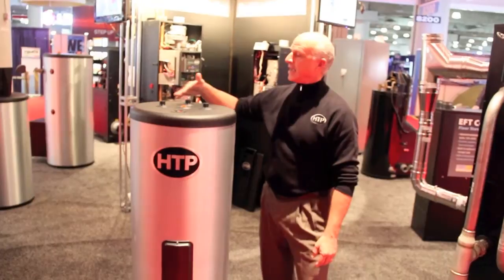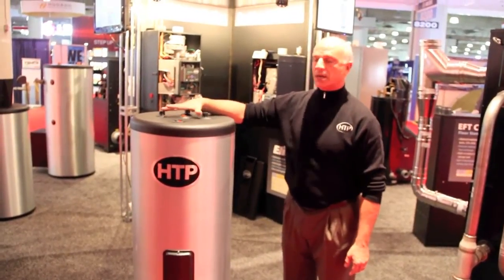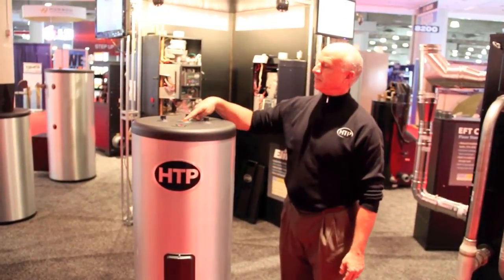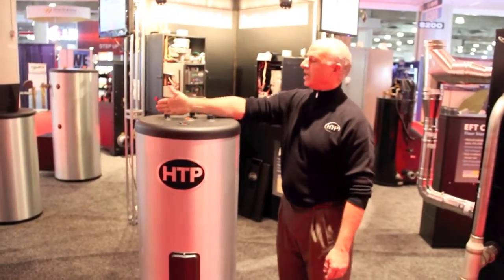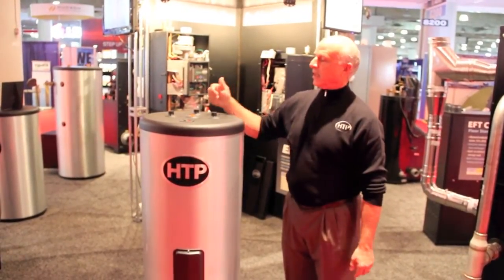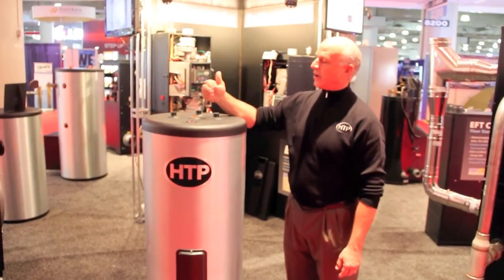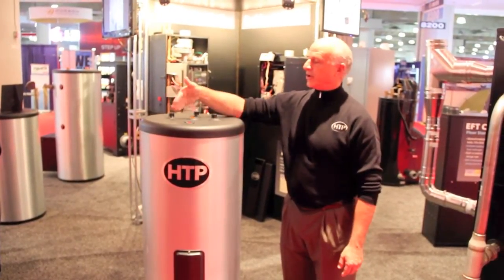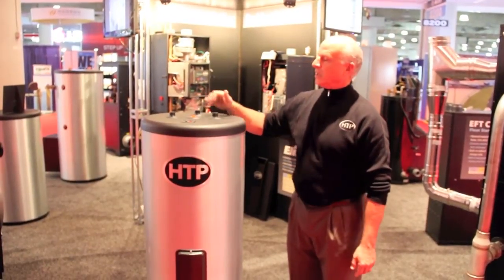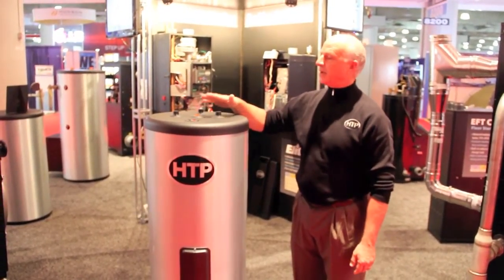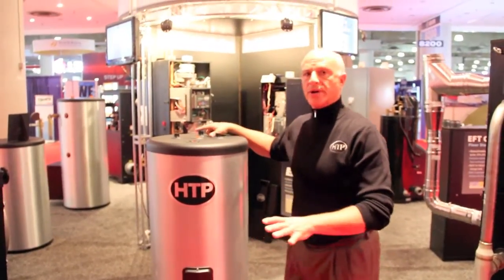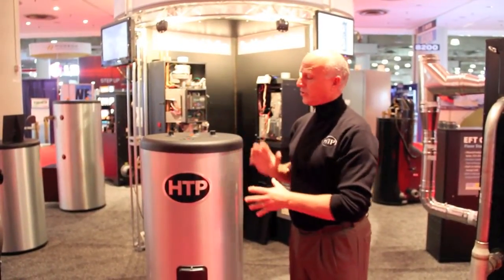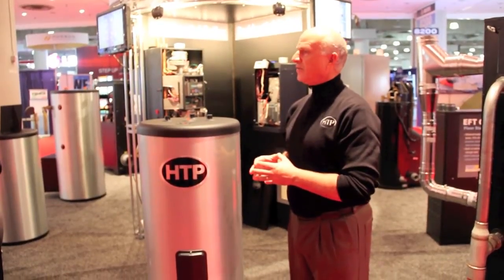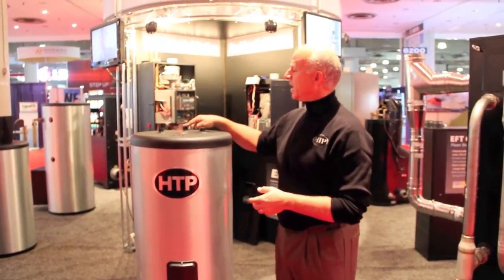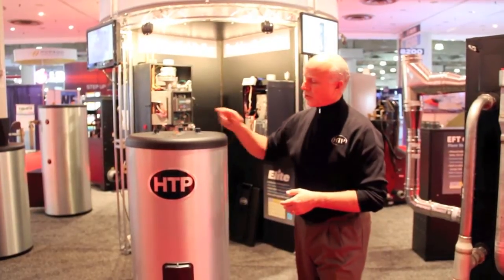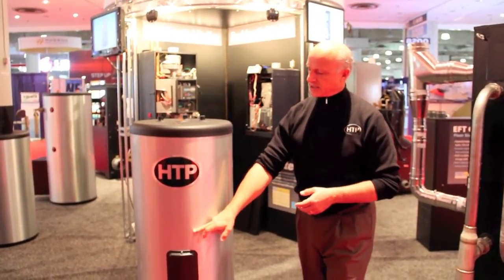We have the top tappings on this product line, the SuperStor Pro, where we have our T&P off the top, so you can position it in any area if you get into tight spots. If it's located in one area, you can bring it into drainage areas and various quadrants of the tank. You'll have your hot and cold tappings off of the top, and a really unique feature that no other indirect has: we really value the performance of our products, and we try to even enhance the value. What we did is add an auxiliary port, and the auxiliary port only goes down to one third of the tank, basically around here.